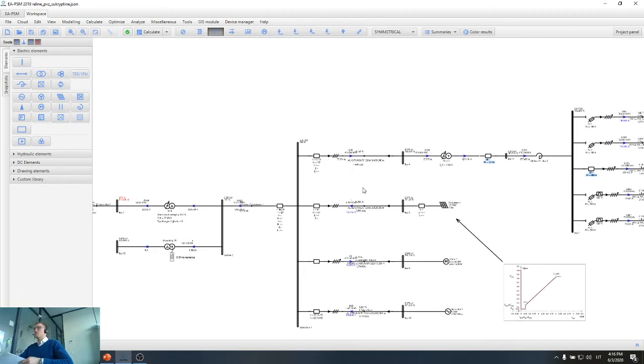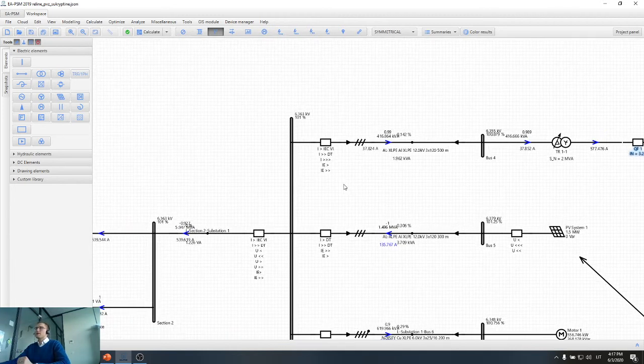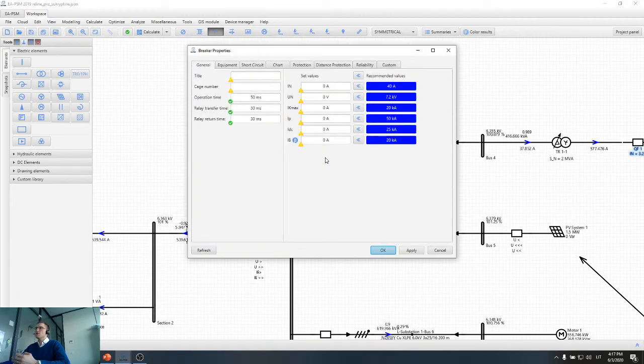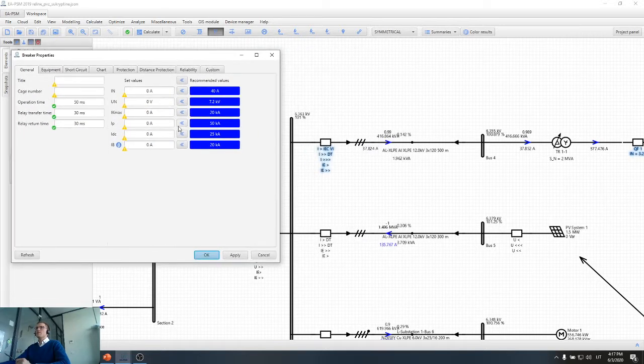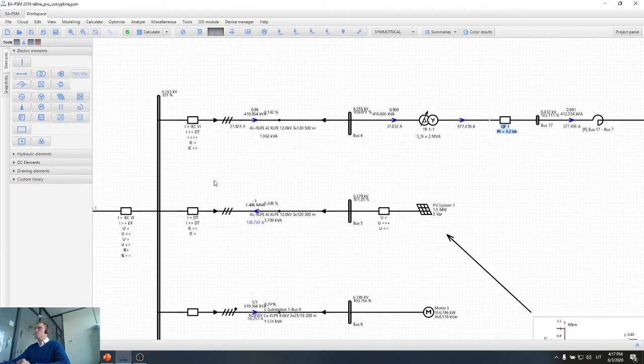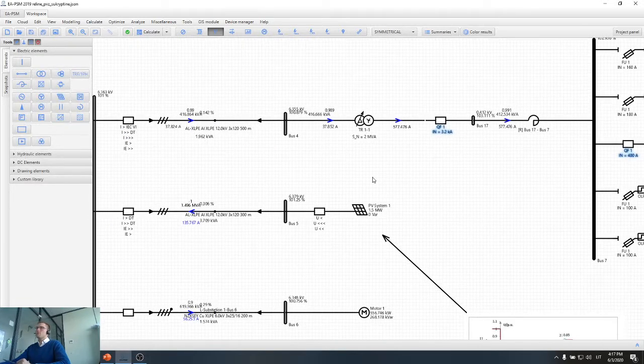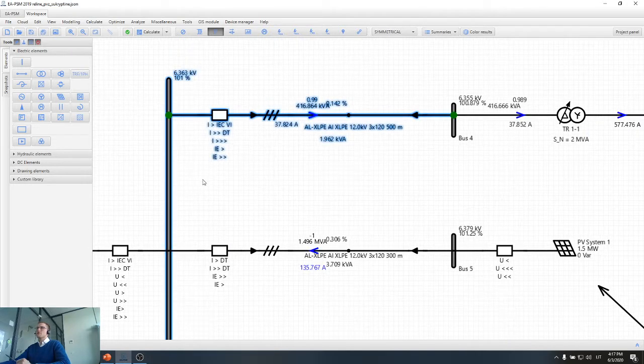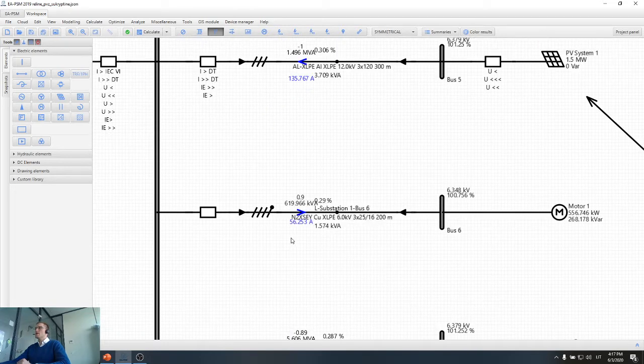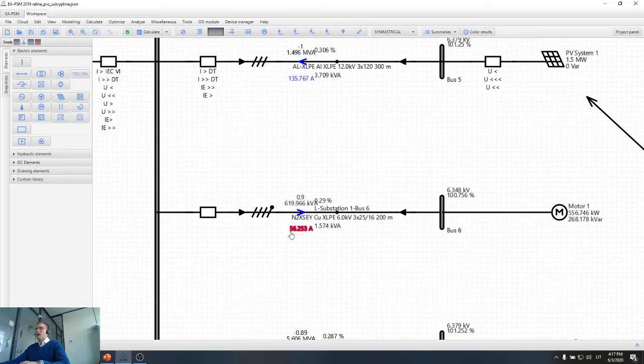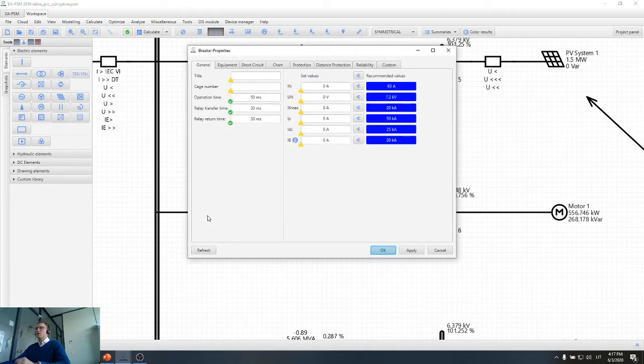So for relays, first of all, what we need to select is the breaker, because the relay is an automation device that needs to control the breaker, which will disconnect the network. So first of all, we need to select the breaker, and in order to select it, we have recommendations from the software. For example, for this transformer breaker, or let's take maybe not the transformer, because here I already have the protections selected. Let's take this motor. The motor current is 56 amps, and when I open the breaker, I can see that I already have recommendations for my breaker.